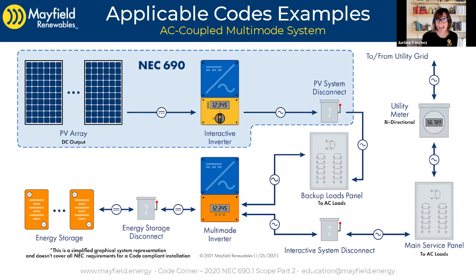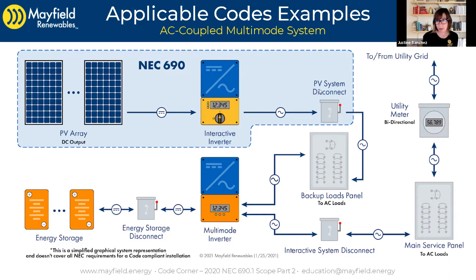Or if you want to utilize a packaged energy storage system — say, maybe the Tesla — where there's an AC output only, you have to AC couple that to a PV system because there is no way to DC couple it. AC coupling essentially means that we are combining our power production sources on the AC side of the bus. The PV system is outputting AC once it goes through the interactive inverter. Our energy storage system, showing batteries with an energy storage disconnect and a multimode inverter, also outputs AC. So we're combining those power sources on the AC side — thus AC coupled.